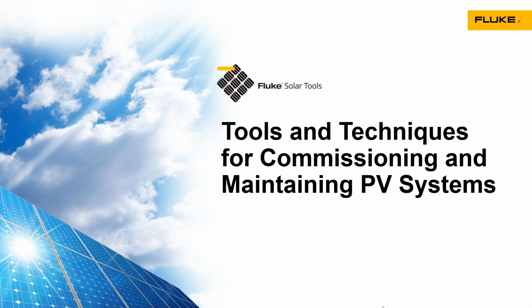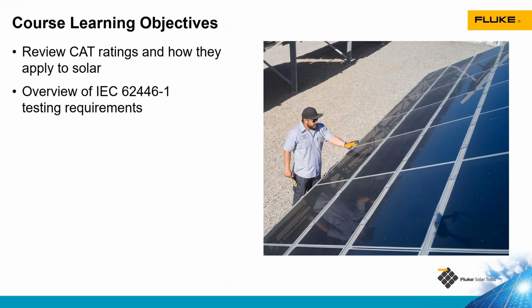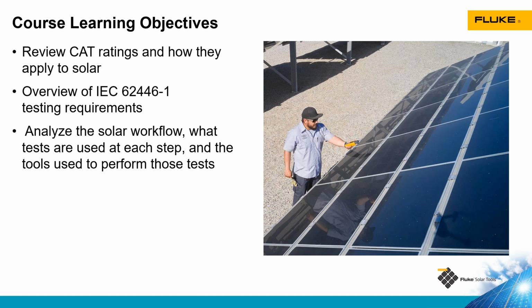In this presentation, I am going to talk about the tools and techniques for commissioning and maintaining PV systems. We're going to start off by reviewing category ratings, voltage ratings, and how that applies to the test tools that we're going to select for doing our testing in the solar industry. I'm going to talk about IEC 62446-1 briefly, which is a standard for testing grid-connected photovoltaic systems. Most of the presentation is going to talk about the tools that are used in testing solar from installation through commissioning and into the operations and maintenance stage of the system.